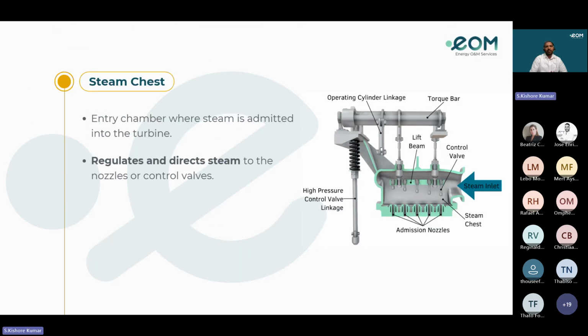Steam chest. Coming to the steam chest, it is the entry chamber where the steam is admitted into the turbine, and it regulates and directs steam to the nozzles or control valves. Here we can see the valve seats, and the valves will open as per the lift. During major outages, it is recommended to test the valves by DP test or ultrasonic to find any cracks, and also change the gland rings of the spindle to avoid steam leakages.